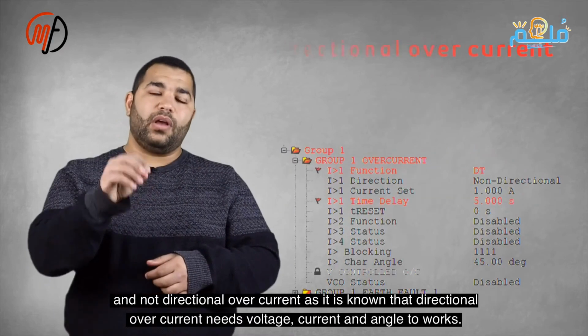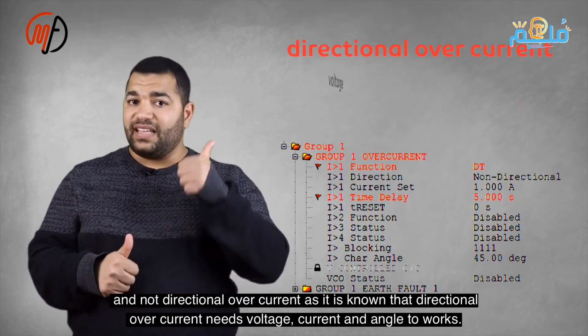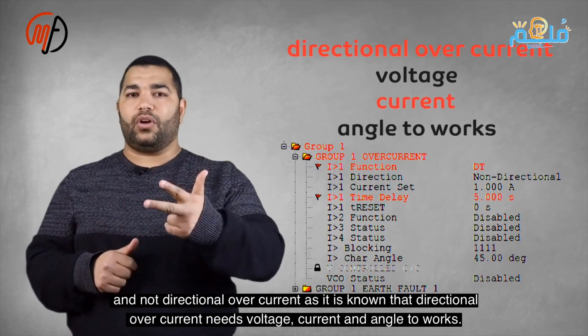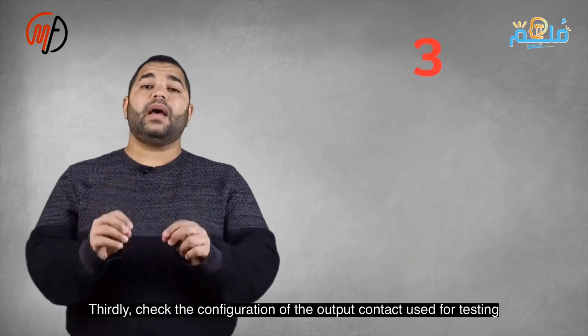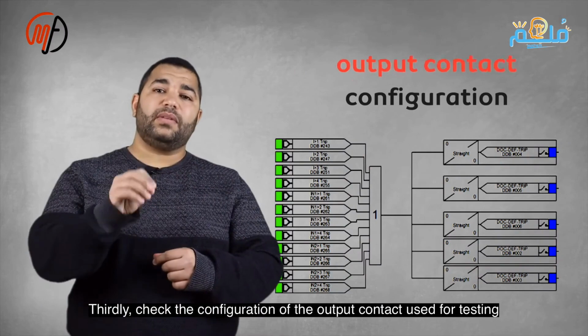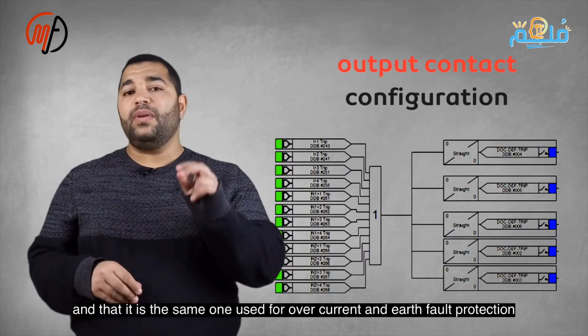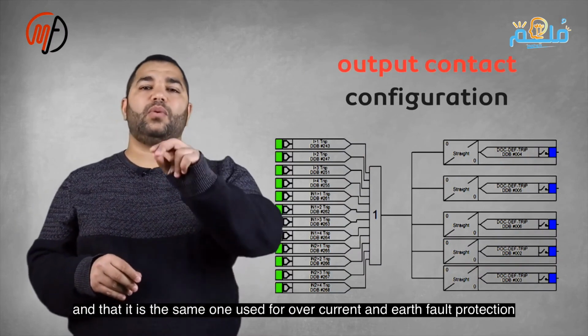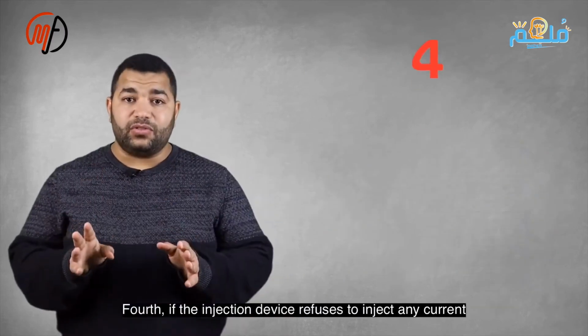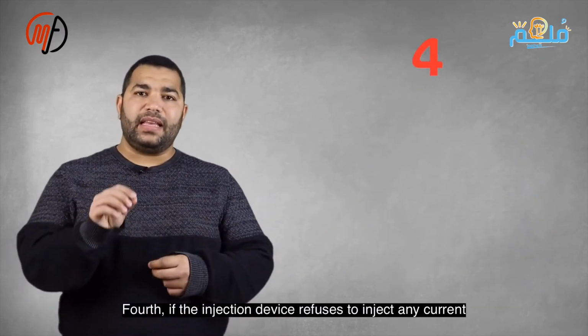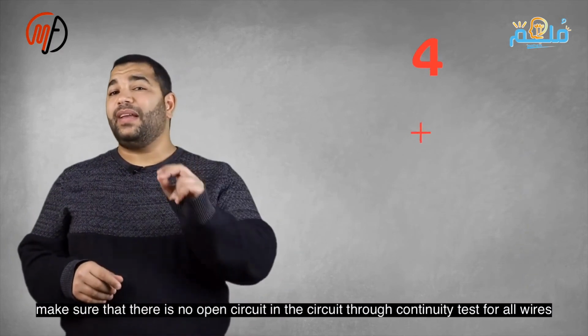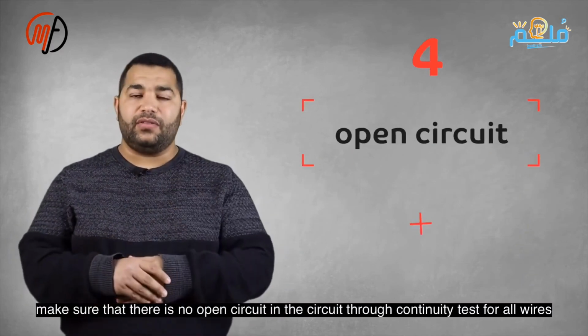A directional overcurrent relay needs voltage, current, and angle. Third, ensure the output contact configuration matches overcurrent and earth fault protection. Fourth, if the device won't inject current, check for open circuits with a continuity test. Fifth, use a multimeter to verify the output value before injecting into the relay. Sixth, if injecting above pickup current and the relay doesn't operate, ensure the overcurrent function is on.